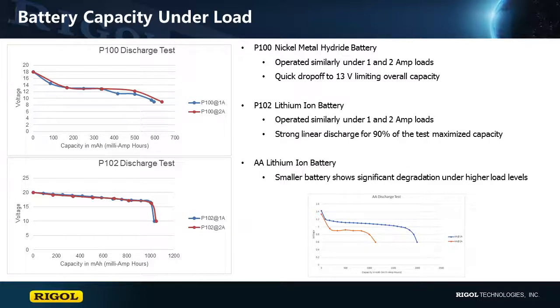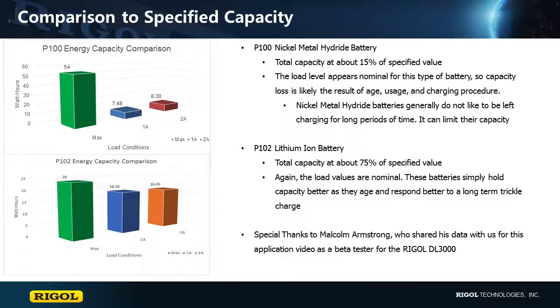Now let's compare these results to the specifications for the batteries. Here we see that the nickel metal hydride batteries are only operating at about 15% of their specified capacity. This is largely due to their age and the charging cycles. Historically, nickel metal hydride batteries do not like to be left on the charger and being charged for long periods of time. It can limit their capacity.